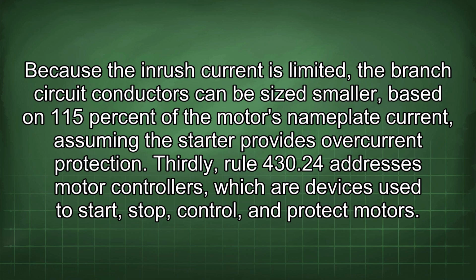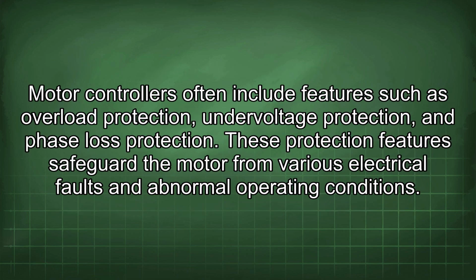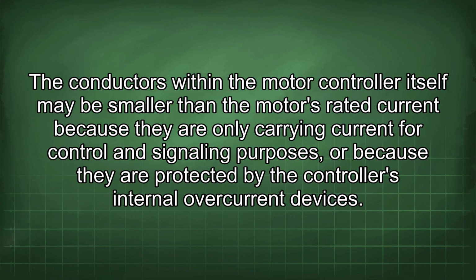Thirdly, Rule 430.24 addresses motor controllers, which are devices used to start, stop, control, and protect motors. Motor controllers often include features such as overload protection, undervoltage protection, and phase loss protection. These protection features safeguard the motor from various electrical faults and abnormal operating conditions. The conductors within the motor controller itself may be smaller than the motor's rated current because they are only carrying current for control and signaling purposes, or because they are protected by the controller's internal overcurrent devices.